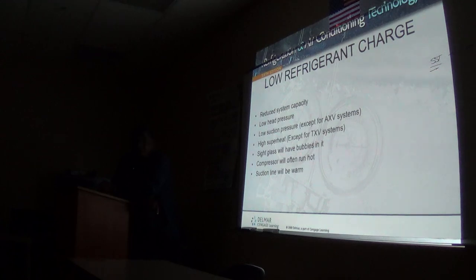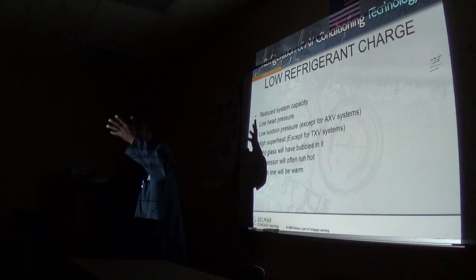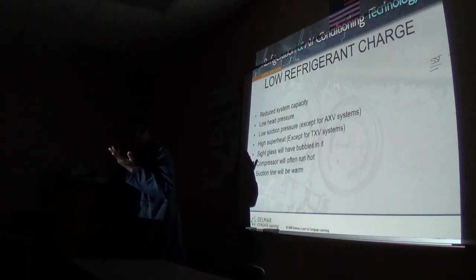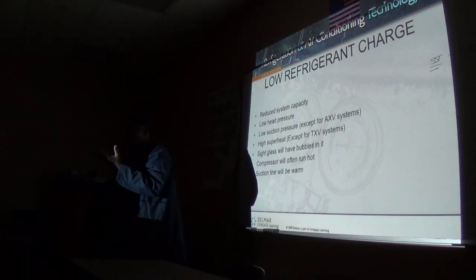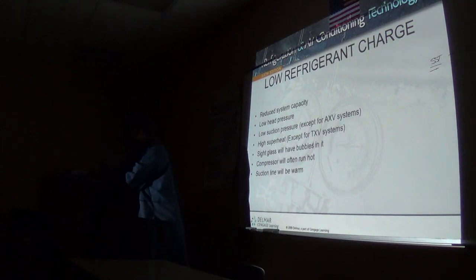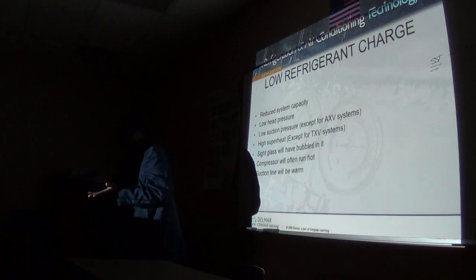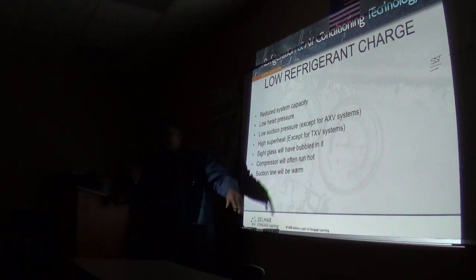Because here's what happens. When the compressor begins to overheat, it breaks down and forms sludge in that oil. Sludge and acid. That acid will be there and create sulfur and all that funky stuff. So if you evacuate, you're not getting rid of everything, but you're getting rid of at least something that will contribute to the compressor going totally bad.